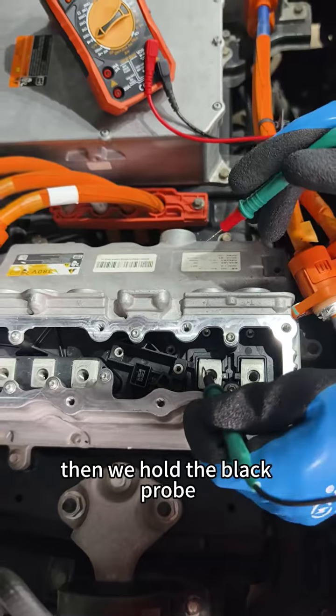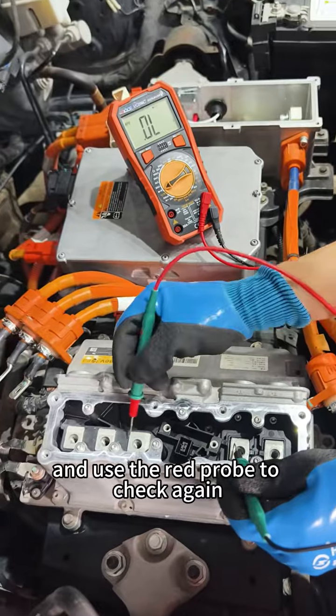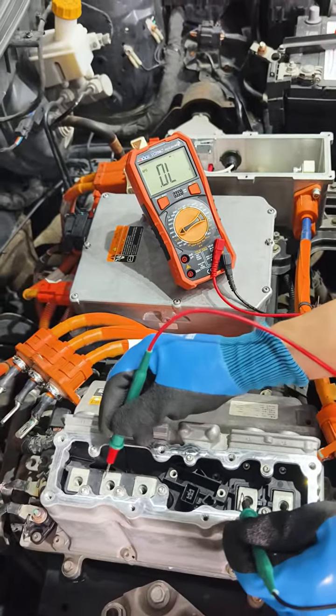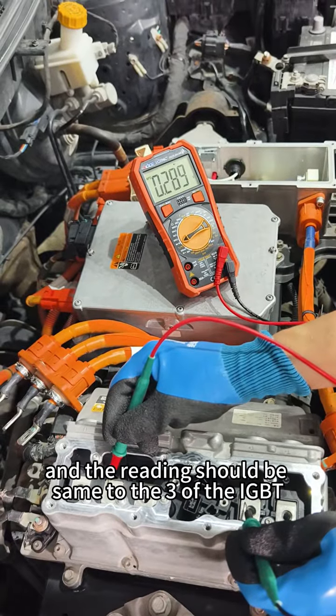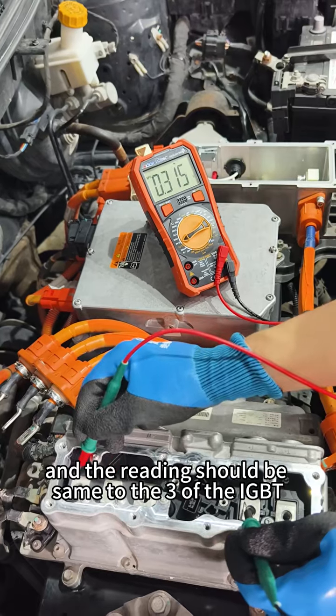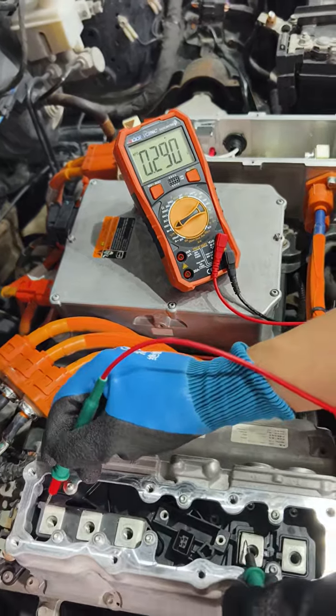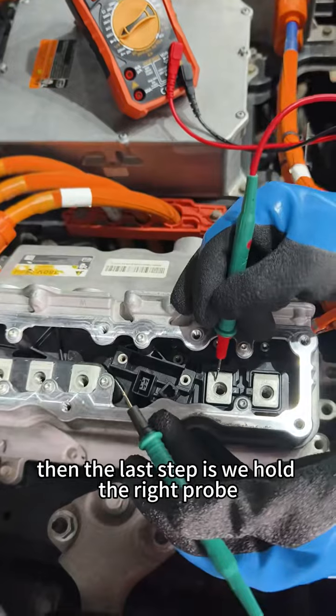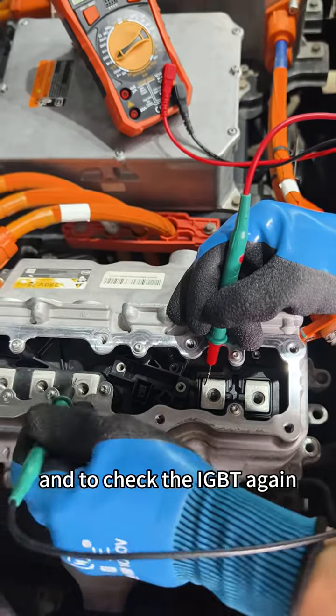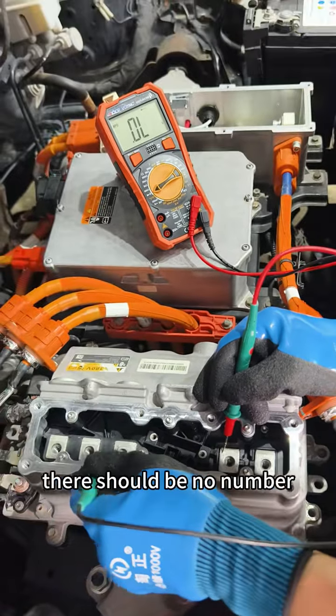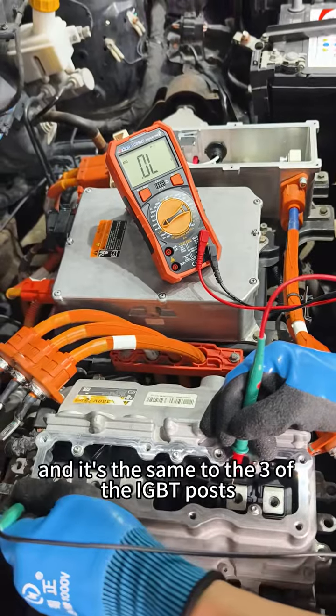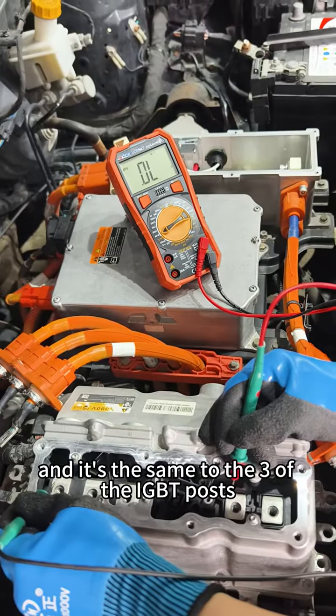Then we hold the black probe and use the red probe to check again. There should be a reading and the reading should be the same for the 3 IGBTs. Then the last step is we hold the red probe and check the IGBT again. There should be no number and it's the same for the 3 IGBT poles.